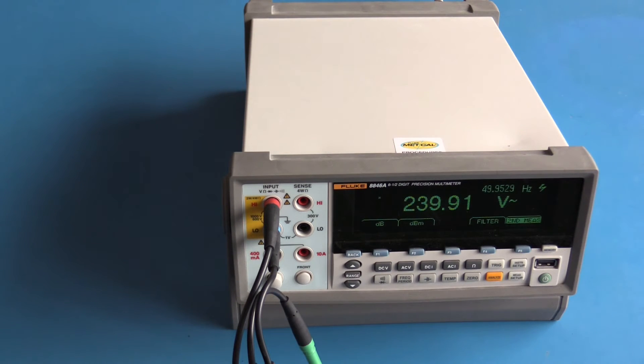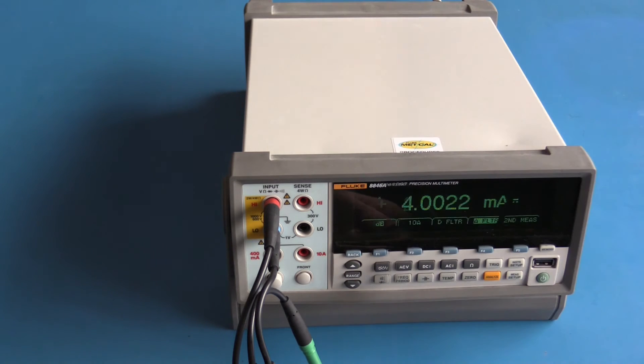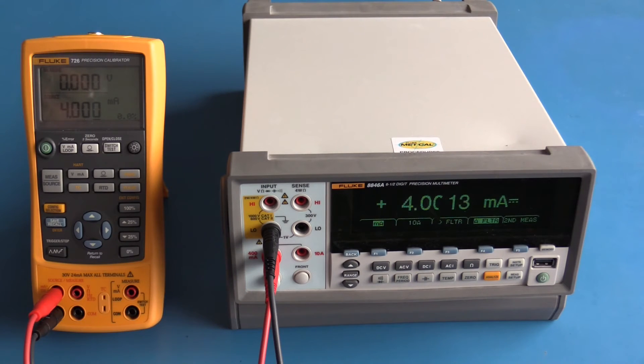The Fluke 726 is now sourcing 4 milliamps. I'm using the 400 milliamp input jack and we're looking at DC current. The meter's resolution is five digits, one PLC integration time, and again these two meters are in quite close agreement with each other.